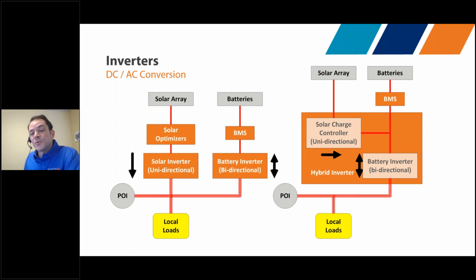On the right-hand side, we wanted to highlight that there are a number of applications today where you can find hybrid inverters, which are a good match for the application. Then you have a single piece of power equipment that includes your MPPT, your solar charge controller, as well as your bidirectional battery inverter. The advantage is you have a single piece of equipment that manages all of that for you. The potential disadvantage is that you then have fixed ratios of power available for that particular solar array and battery power bandwidth.